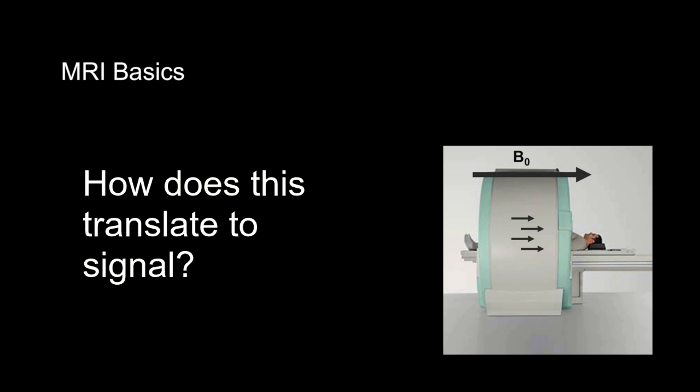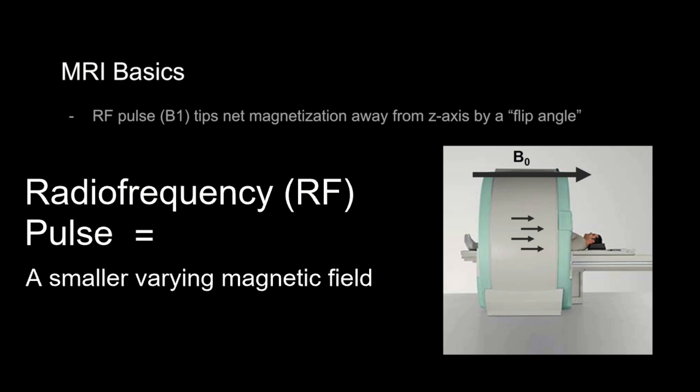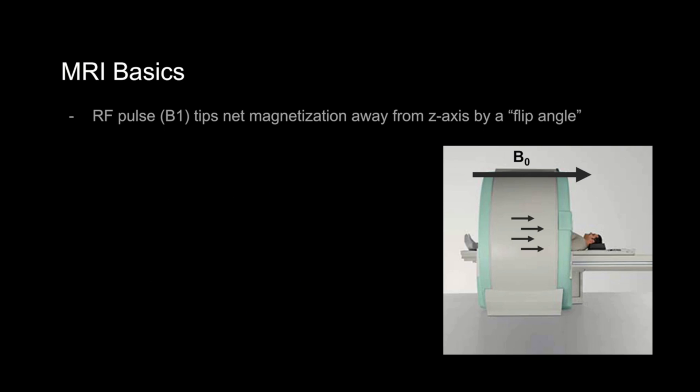So, how do we translate this into MRI signal? Next, we apply something called a radio frequency pulse, or RF pulse, that is designed to tip the net magnetization away from the z-axis. The RF pulse is essentially a smaller, varying magnetic field applied at a specific frequency in a direction that is perpendicular to the main magnetic field. It's not really a radio wave, but instead it's electromagnetic energy with a frequency that is in the radio wave spectrum.